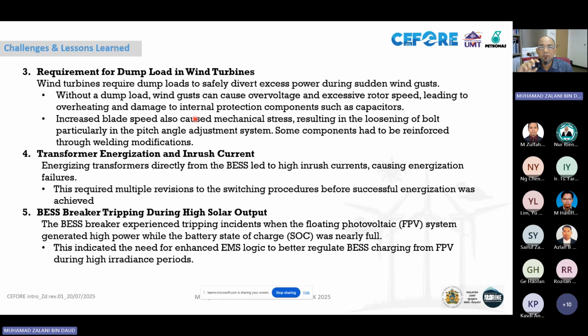Then it affects the protection system of the wind turbine itself. Some of our experience during commissioning of the wind turbine, when subjected to wind gust, is that it caused some of the capacitors to burn out, and some bolts were loosened, especially where the mechanical part got stressed at the pitch angle adjustment system. So we retrofitted it by using welding. So now we are ordering the dump load, and we will install the dump load at 4 units of our wind turbines. Basically, this is something that we have learned.